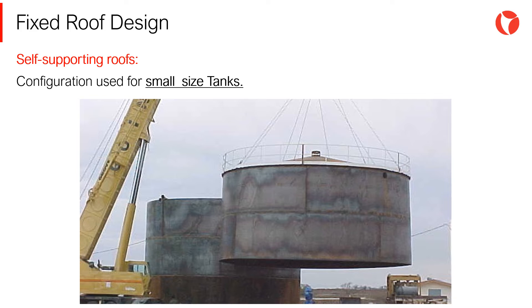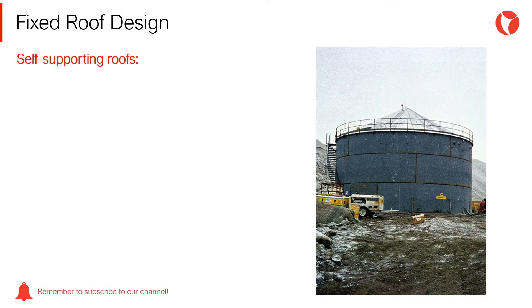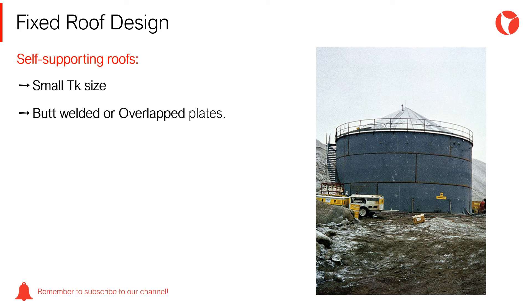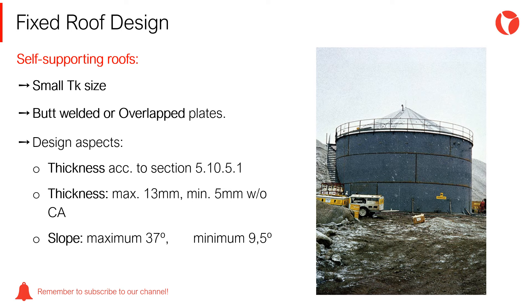Self-supporting roofs can adopt any of the three configurations mentioned earlier: conical, dome type, or umbrella type. The main characteristics of self-supporting roofs are that they are used for small tank sizes; roof plates are normally butt-welded but can be overlapped. Regarding the design, the thickness is calculated according to section 5.10.5.1, with a maximum thickness of 13 mm and a minimum thickness of 5 mm without any corrosion allowance. The maximum slope is 37 degrees and the minimum slope is 9.5 degrees.